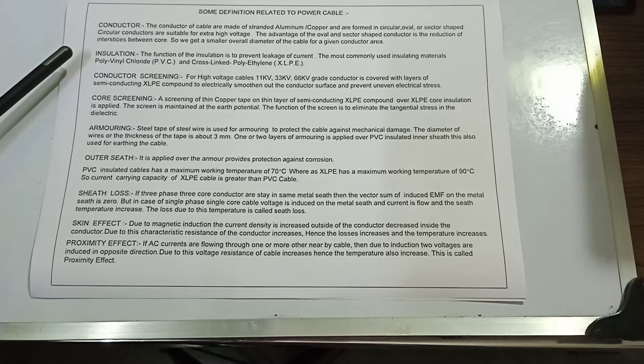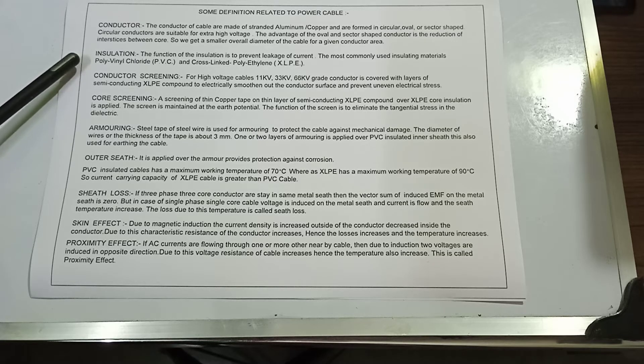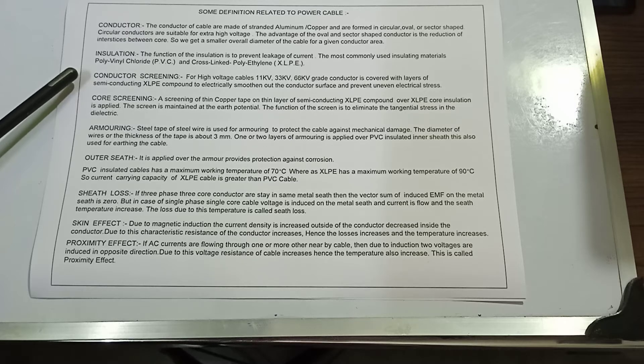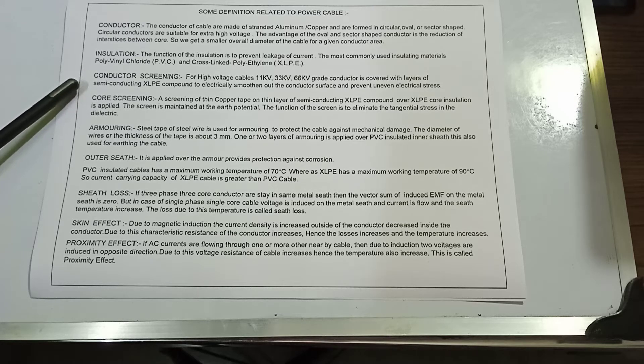This gives a smaller overall diameter of the cable for a given conductor area. Next: insulation. The function of insulation is to prevent leakage of current. The most commonly used insulating materials are polyvinyl chloride (PVC) and cross-linked polyethylene (XLPE). Next: conductor screening. For high voltage cables — 11 kV, 33 kV, 66 kV grade — the conductor is covered with layers of semiconducting XLPE compound to electrically smooth out the conductor surface and prevent uneven electrical stress.